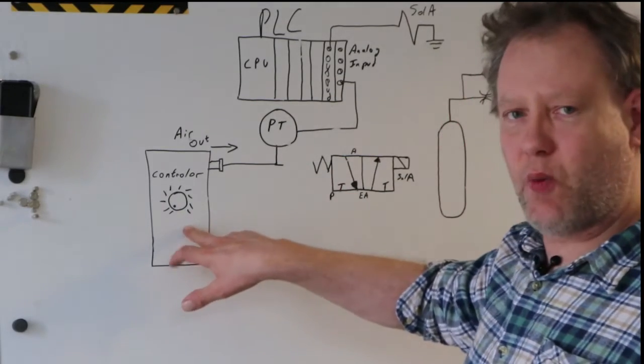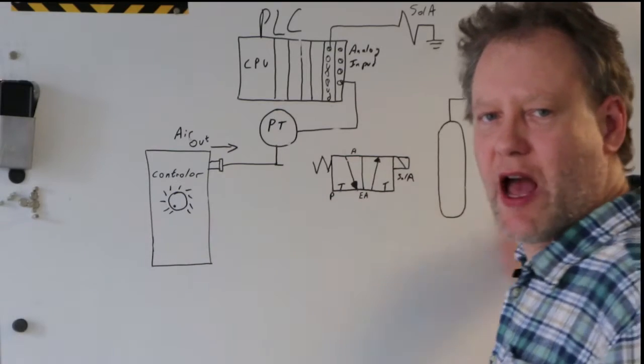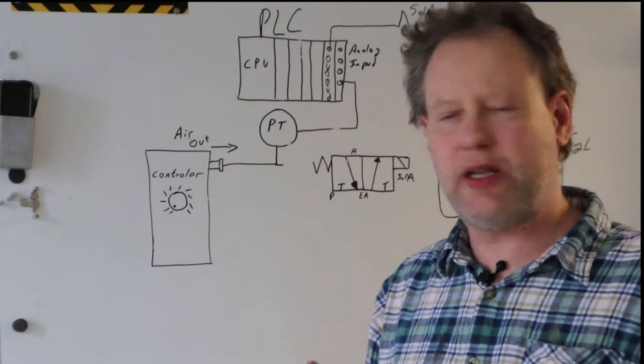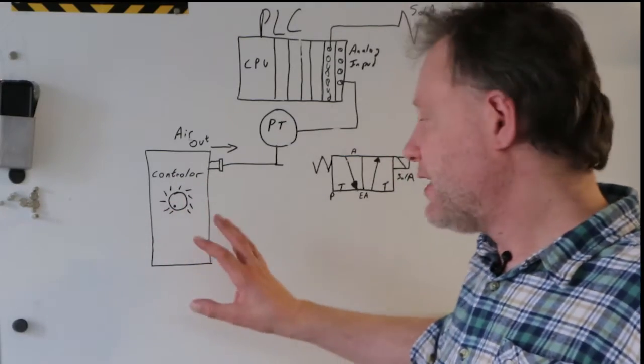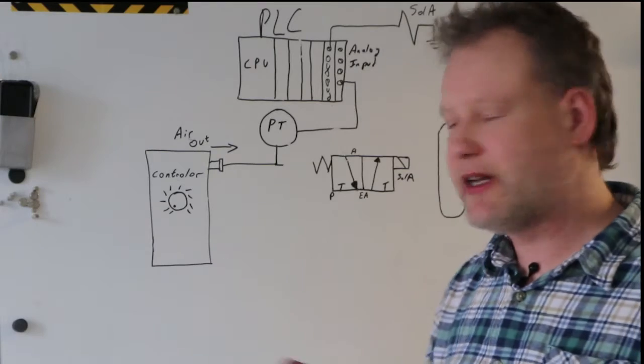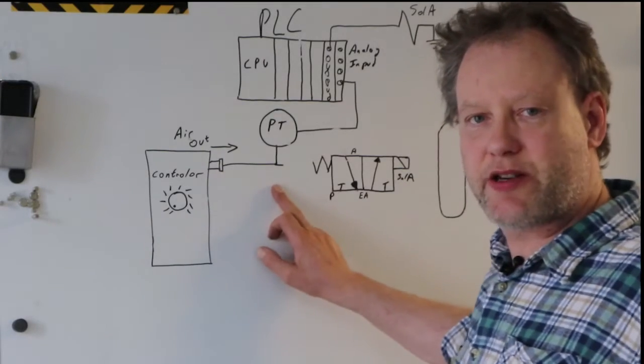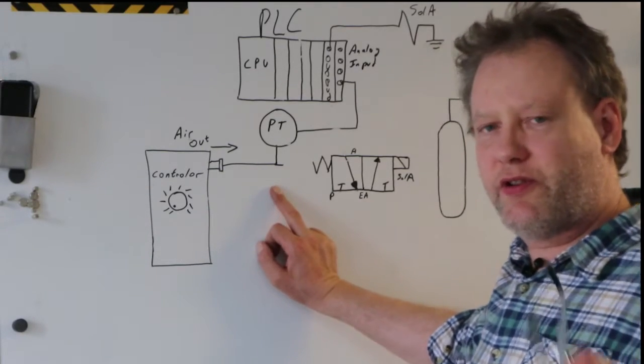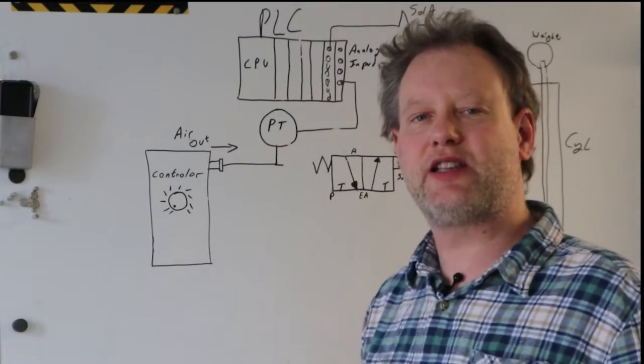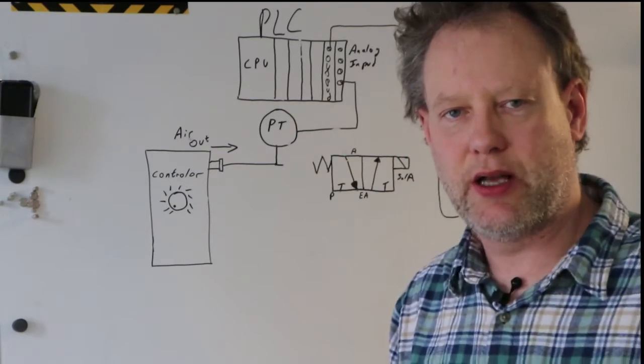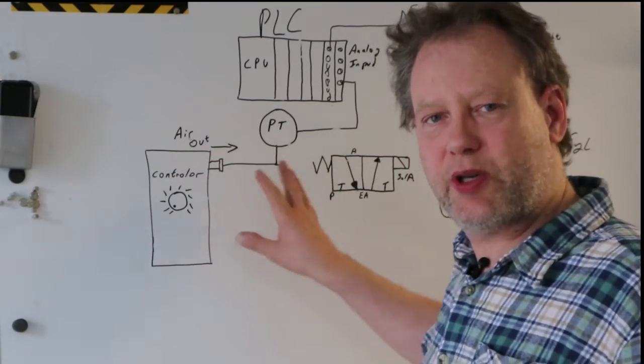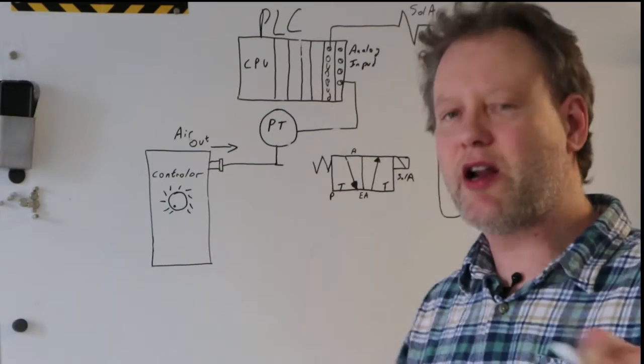I want to do two things with this. One is I want to run it through its paces so it's driving this pneumatic muscle over and over and over again for about five hours. I really want to push this medical controller. So the only thing that's really important about this is that it does send out pressurized air. So the two things are, one is I want to send it through its paces, but beforehand I want to test the full load pressure. I want to see how much pressure the little diaphragm pump that's in here puts out at the beginning of the test.